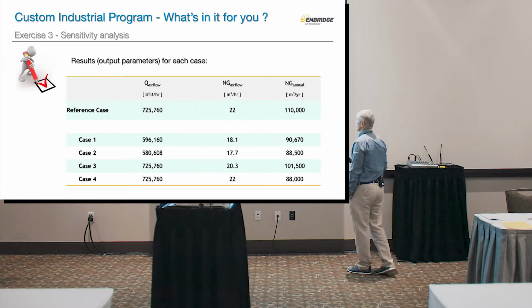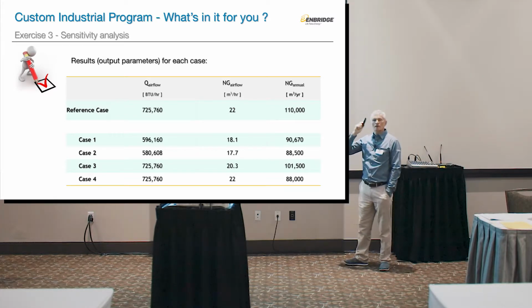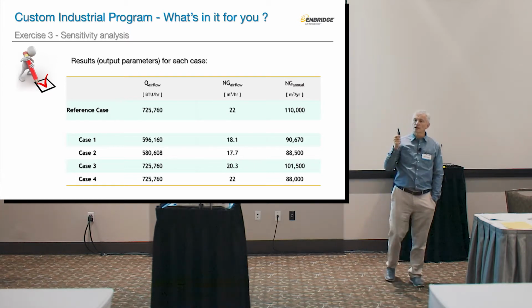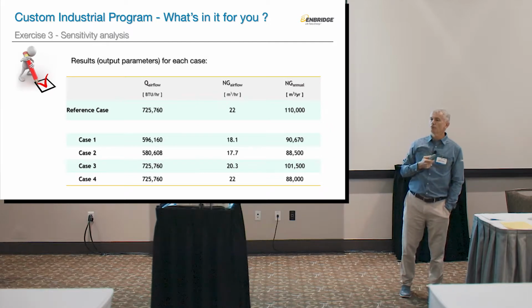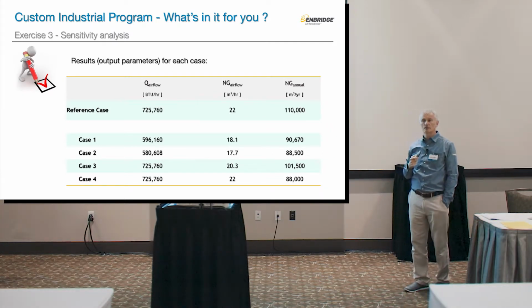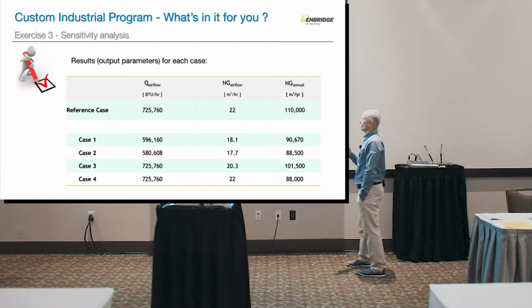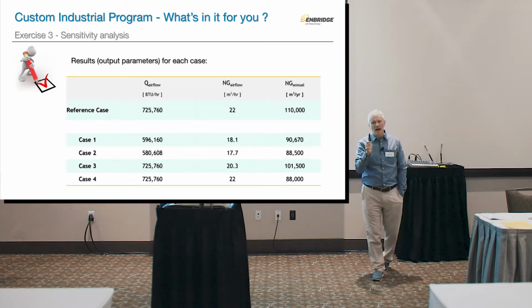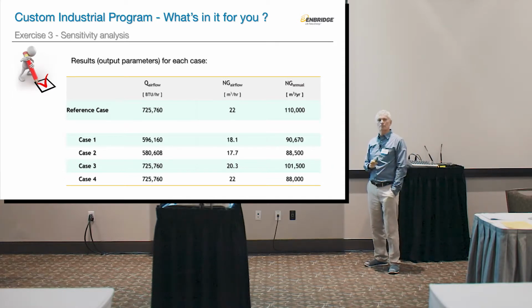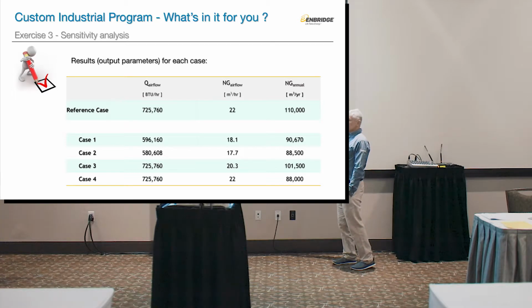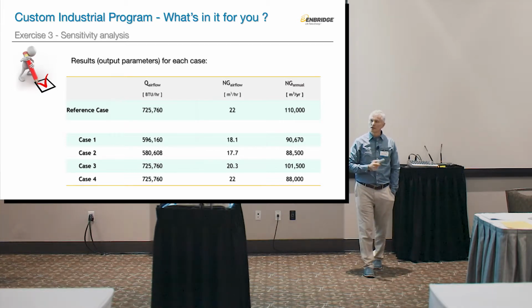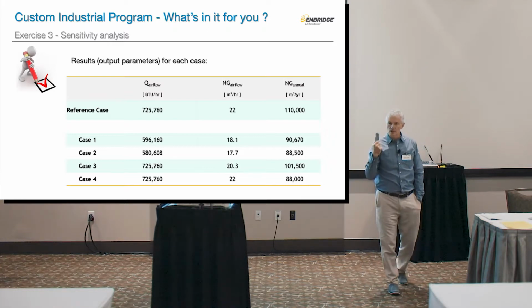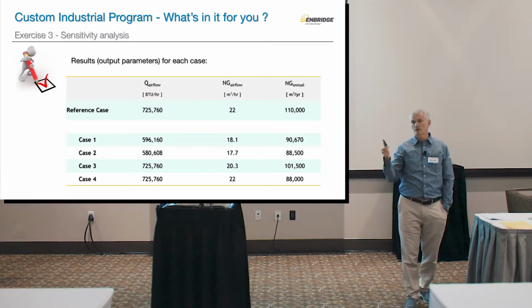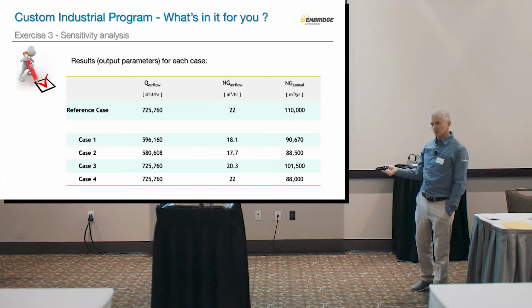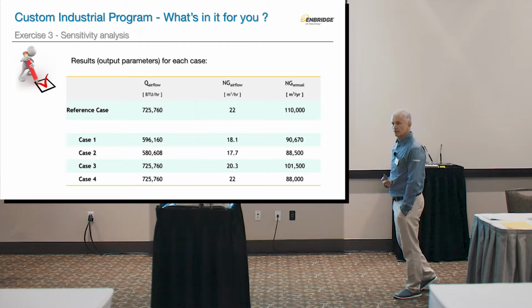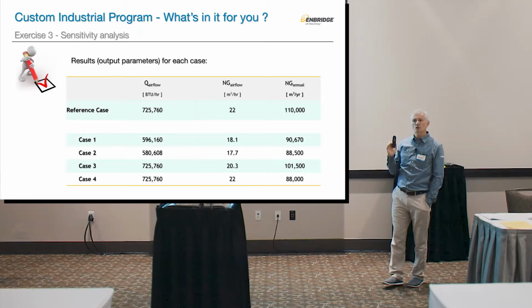However, what is a big deal is what we see most. When we talk about makeup air units, people are terribly afraid to turn them off, even when there's nobody in the facility. They'll say, I don't want to turn off this 20,000 CFM makeup air unit, I'll leave it at 20%, I'll just take off 20% when nobody's there. But you're still using 88,000 cubic meters a year when nobody's in the facility. Think about it, a makeup air unit makes up the air that the process is using. If there's no people, there's no process, there's no need for makeup air. But people turn it on because they don't want things to freeze.